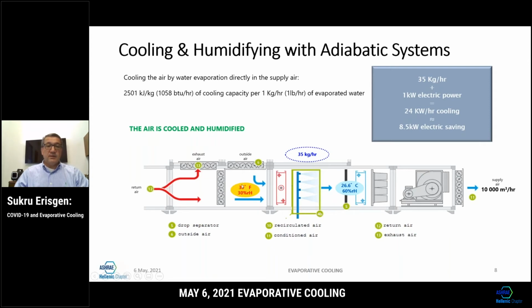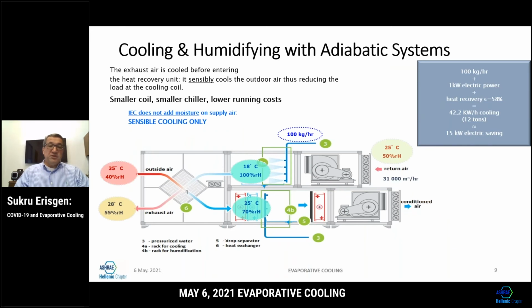As you can see, the air enters at 35 degrees at 30% relative humidity. After the misting stations, evaporative cooling, it can go down to 26.6 degrees at 60% relative humidity. Sometimes designers can add heating coils. Either it can be a condenser or just direct heating, and then a DX cooling coil can also be added here. To improve the efficiency, we can also add a heat exchanger here.